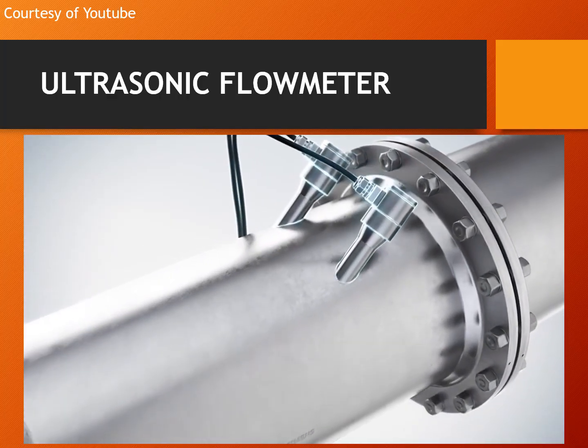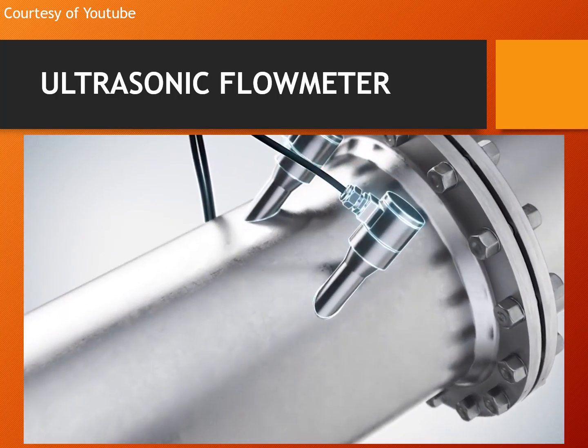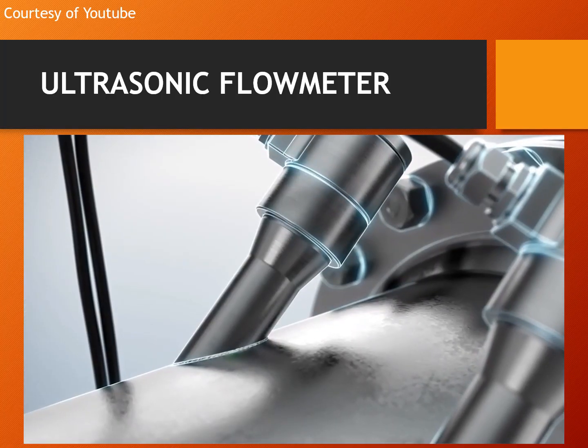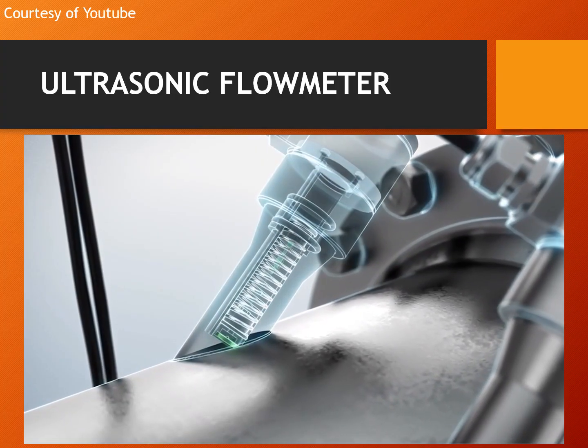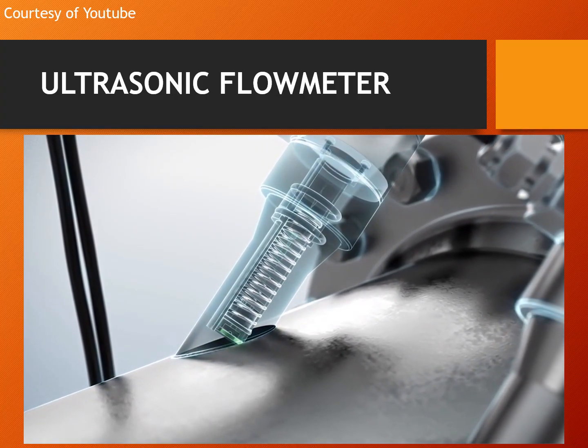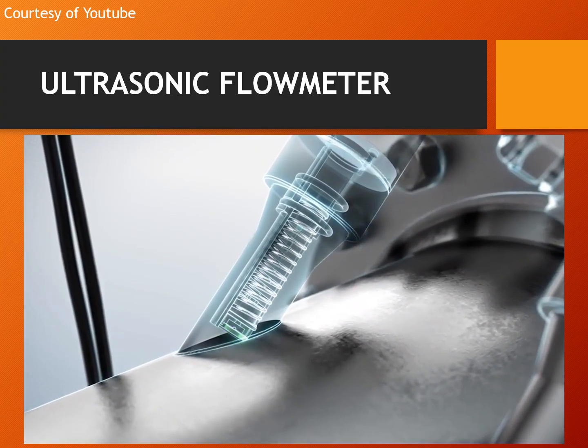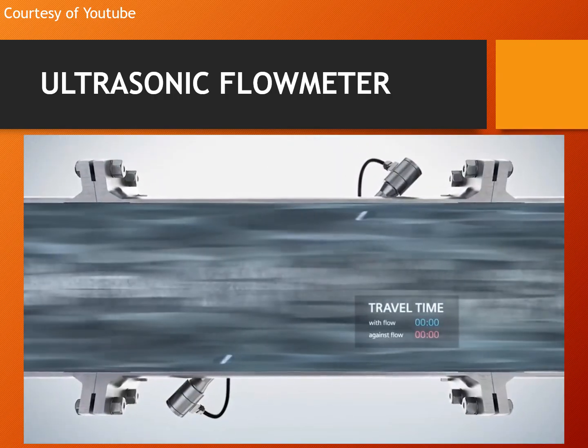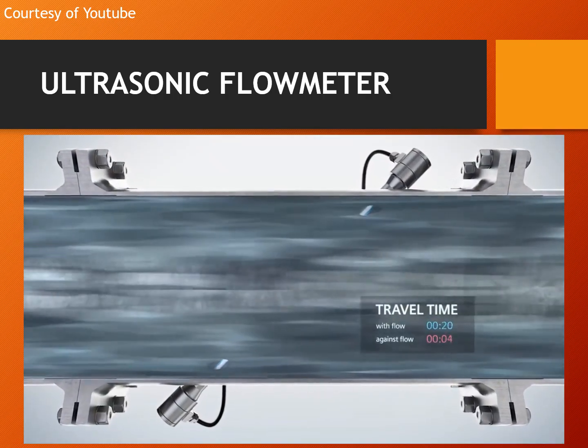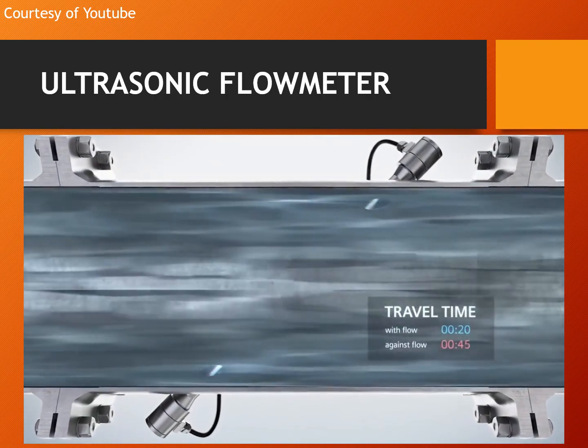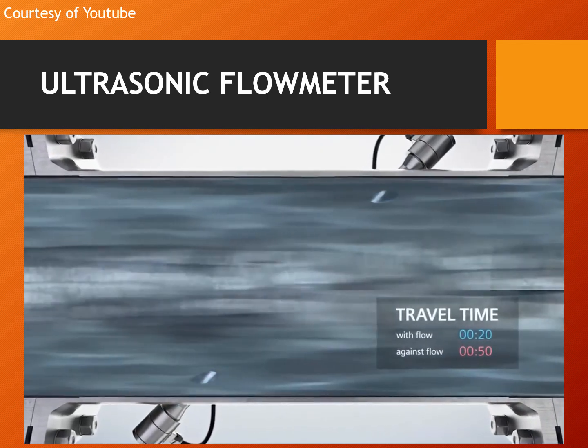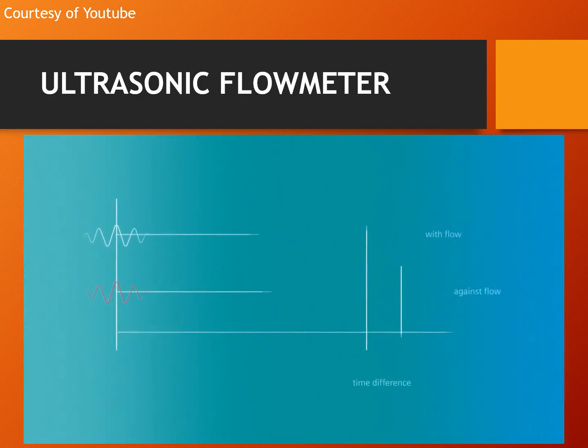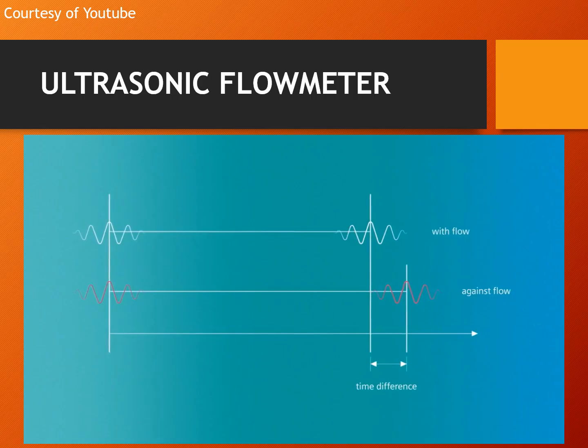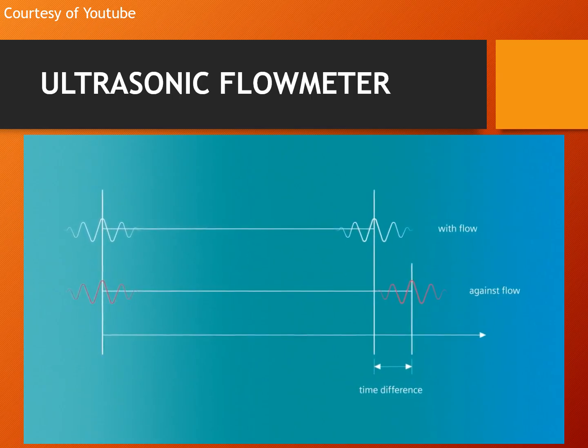Ultrasonic waves are alternately sent and received by means of the piezoelectric effect, where mechanical energy is converted into electrical energy through the use of a crystal. When moving in the same direction as the flow, they travel faster than waves traveling against the direction of the flow. The higher the flow velocity of the medium, the greater the difference between the two transit times.